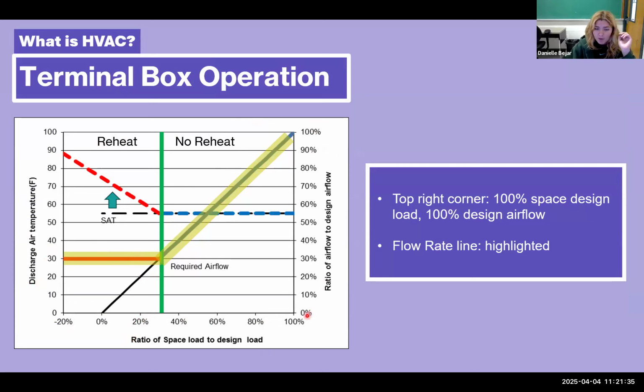So here for terminal box operation, you can see the top right corner here is your 100% design load and 100% design airflow. So given your certain load, you want to get to 75 degrees Fahrenheit, 50% relative humidity. This 100% is the airflow that's needed to do that. And so as your load decreases, your airflow can decrease until you get to this minimum airflow rate, which here is 30%. And that's to maintain adequate ventilation. So you need at least 30%. And we're going to manipulate this number here.